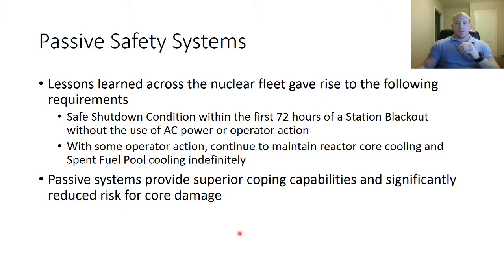And drawn from lessons learned across the operating fleet, when they were designing the AP1000, they wanted the requirement that the passive safety systems can safely shut down their core within the first 72 hours of an accident, during a station blackout, without the use of AC power or operator action. And then with some operator action, it can continue to maintain reactor core cooling and spent fuel pool cooling indefinitely.